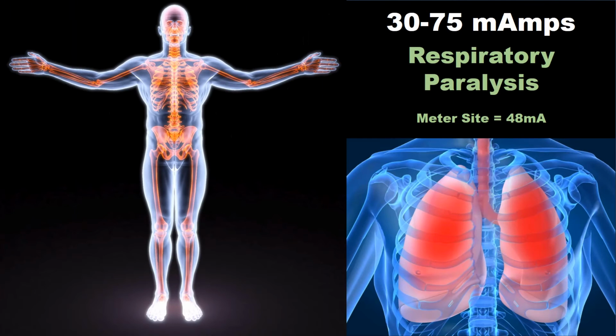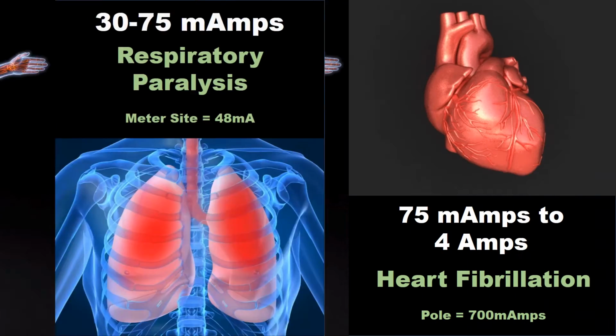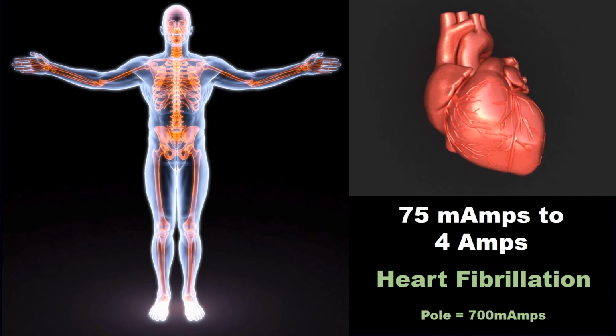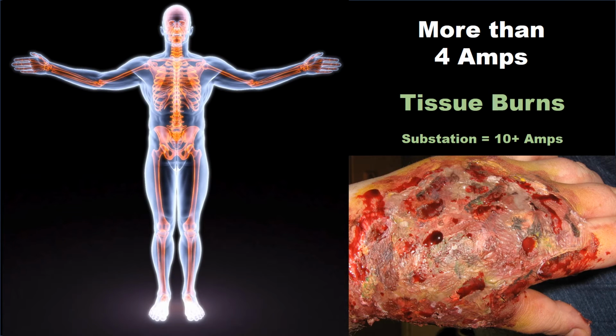At the meter site, where we expect to see 48 milliamps of current, it takes only 30 to 75 milliamps to stop your breathing. At the pole, where we expect to see 700 milliamps of current, it takes only 75 milliamps to 4 amps to stop your heart. At the substation, where you're working around more than 10 amps, anything more than 4 amps will cause tissue burns.